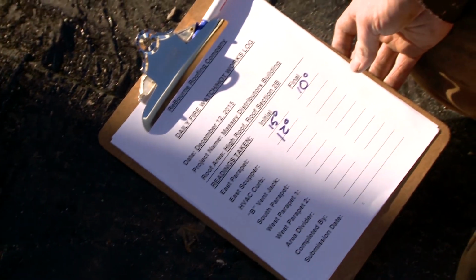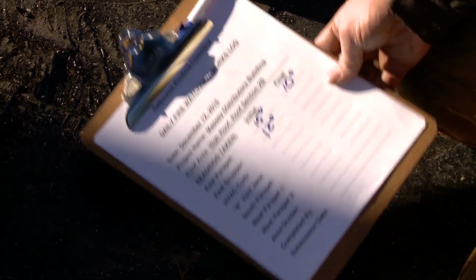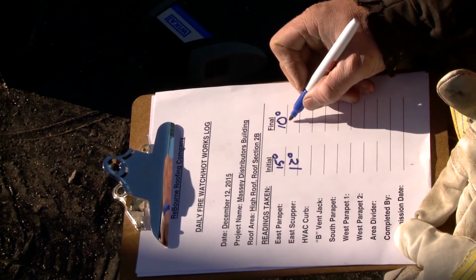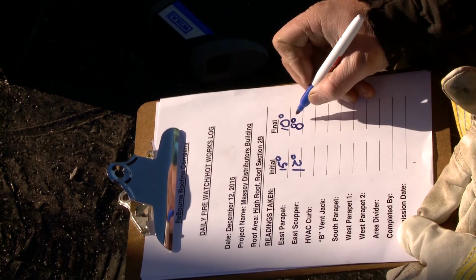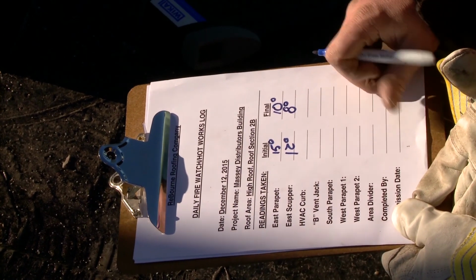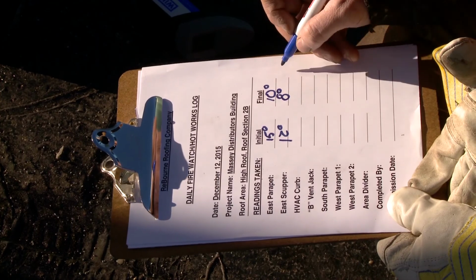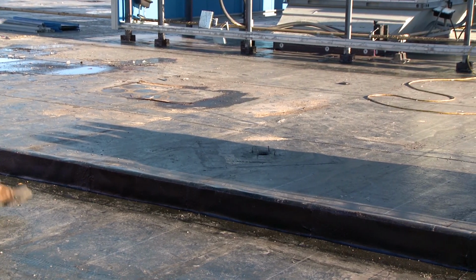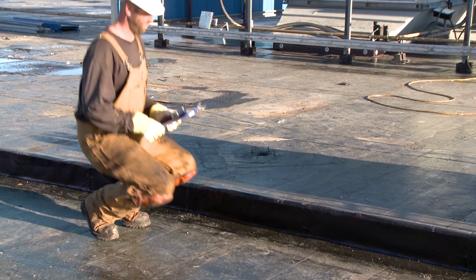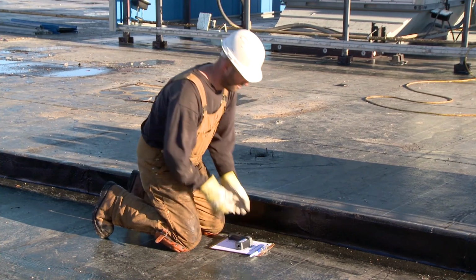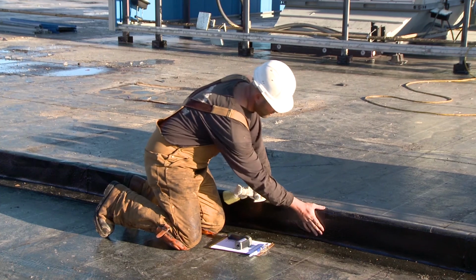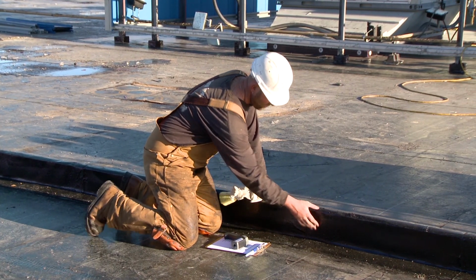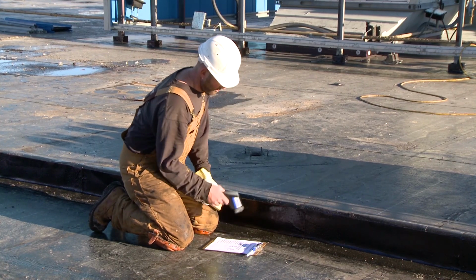Workers must not perform a fire watch alone in the dark, as this practice is unsafe, as assistance is not readily available in the case of an emergency, injury, or illness. Fire watches are required when workers are leaving the roof work area, particularly during lunch or coffee breaks. It is recommended that at the end of the day, the interior of the building be walked prior to leaving the site. Fire watches need to be recorded on a Fire Watch Job Procedure Form.